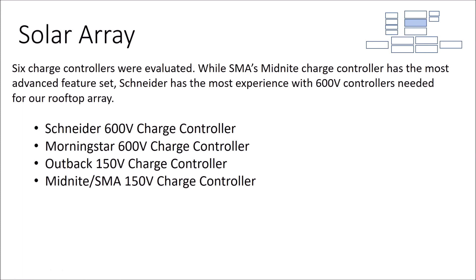We went with a Schneider charge controller and a Schneider inverter because it just makes sense. You stick within the product line, you don't mix and match, so that when it comes to monitoring, everything can show up on the same central display. Each of the charge controllers had two inputs. And so we talk about string sizing, how many circuits go on which inverter. This Schneider charge controller has two circuits up to 600 volts each.